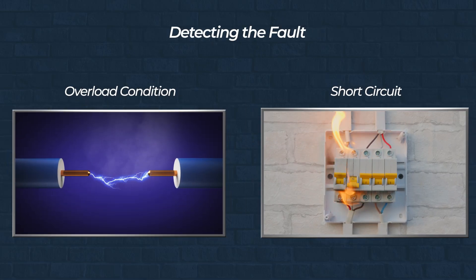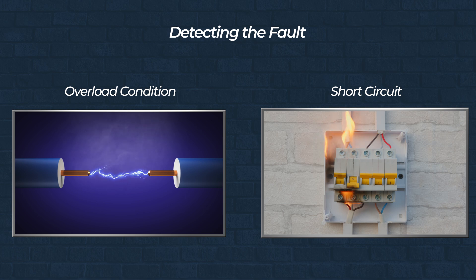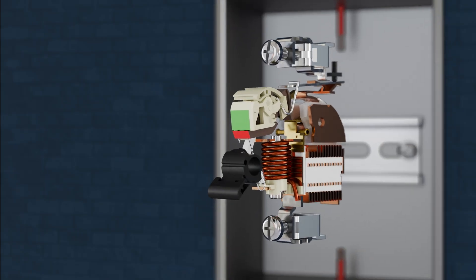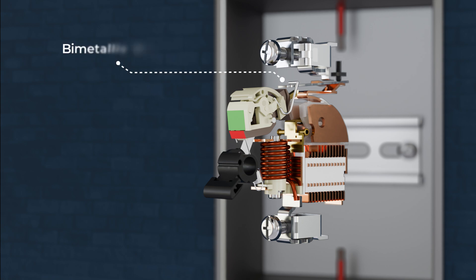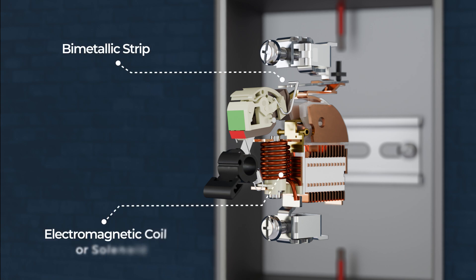MCBs are designed to protect against two primary types of faults: an overload condition — a moderate overcurrent that lasts for some time — and a short circuit, a very high current surge occurring almost instantly. Inside an MCB, two key components are responsible for detecting and responding to these faults: the first is the bimetallic strip, for overloads; the second is the electromagnetic coil, or solenoid, for short circuits.